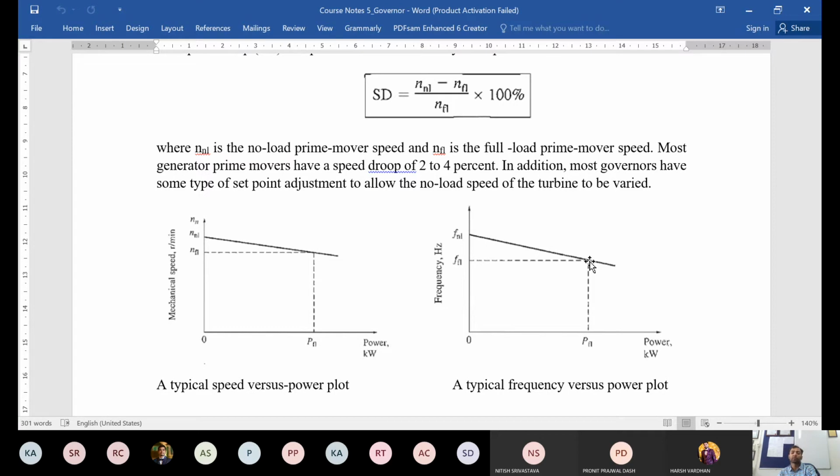So 49.9 to 50.1. That is the ideal condition. At worst case, even in the worst performance case, maybe plus minus 0.5, or even worst of worst case plus minus 1. That is it. So the range of frequency deviation allowed is very stringent, it is very low. So ideally what we would want is that this frequency remains constant, neither shifts up nor goes down.